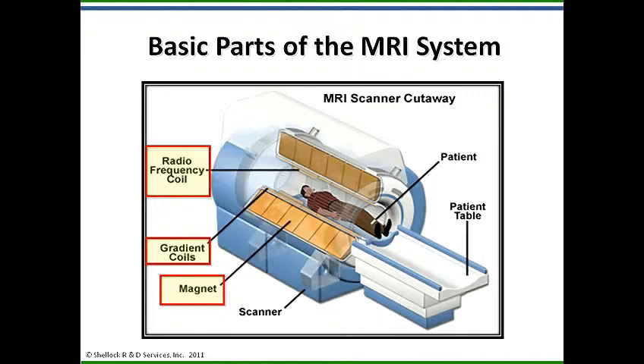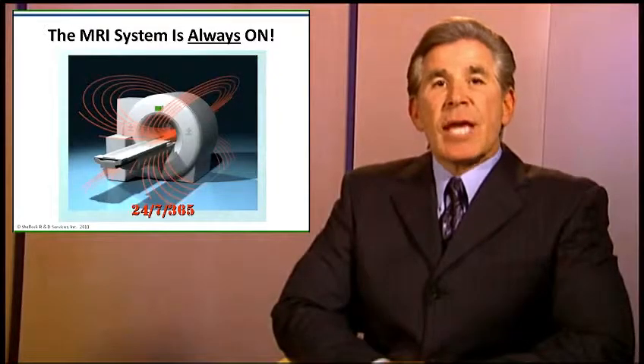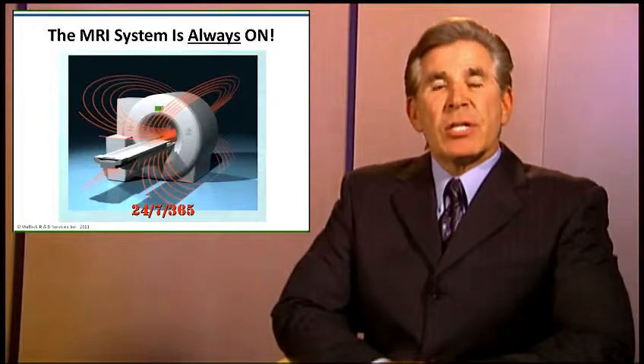Here is a diagram showing the basic parts of a typical MRI system, which may also be referred to as the scanner. Note the most important components of this system, which include the extremely powerful magnet, the gradient magnet coils, which generate rapidly changing magnetic fields, and the radio frequency or RF coil.